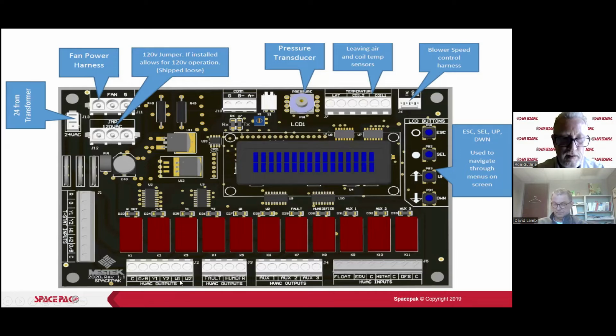W1 is actually, and keep in mind that up in New England where SpacePak's located, their main offices, up there, they're heavy-duty hydronic people, and they don't run heat pumps and auxiliary heat at the same time that often. Because they have a lower design temperature up there, they get to the point where they cut to backup heat, and typically that's hydronic. So this W1 terminal down here at the bottom is really looking for a signal from this coil 2 sensor. Okay, it's looking to determine, well, hey, when should I bring the fan on? You know, when is that coil going to be a warm coil, and I'll bring the fan on at that point. So on electric heat, always use W2.